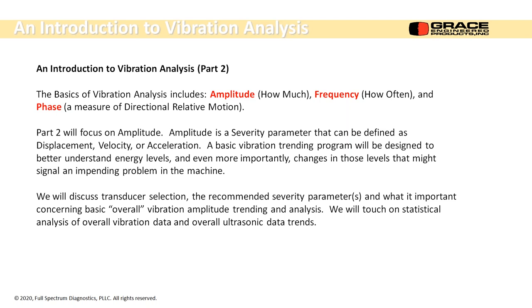In part two, we're going to focus on amplitude, and amplitude is a severity parameter. We can trend displacement, velocity, or acceleration, and we can do any one of those. There is a preferred parameter, and we'll talk more on that. So the basic idea is understanding the energy levels and how those levels might impact the machine. Then we're going to talk a little bit about transducers, recommended severity parameters, overall vibration trending and analysis, and some statistics. I want to lead into ultrasonic data trends, and we're going to probably get into that next Tuesday.